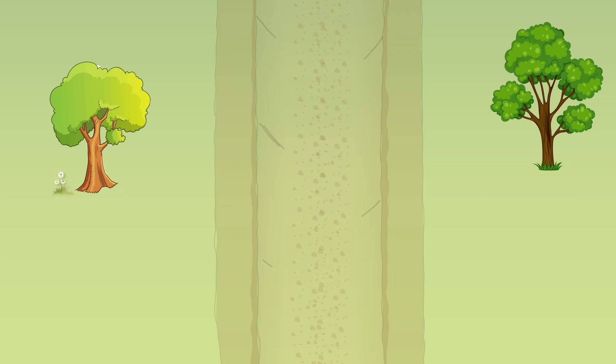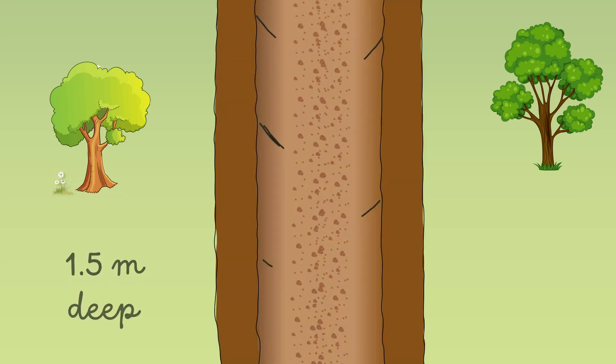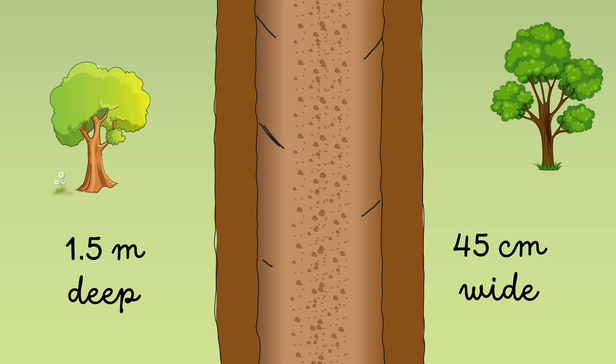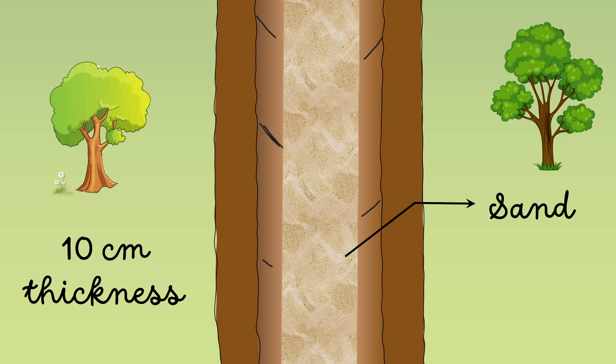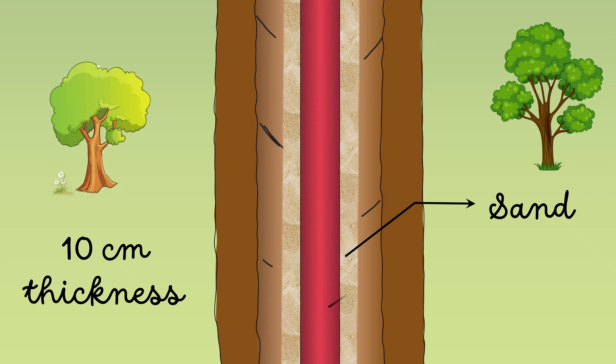In this method, a trench of about 1.5 meters deep and 45 centimeter wide is dug. The trench is covered with a layer of fine sand of about 10 centimeter in thickness. The cable is laid over this sand bed.